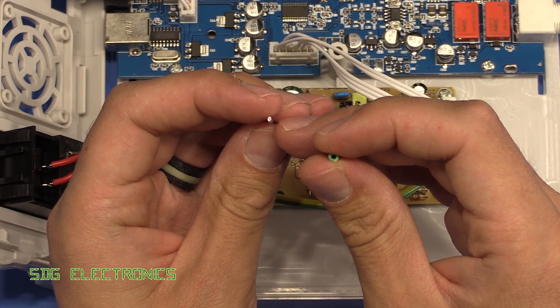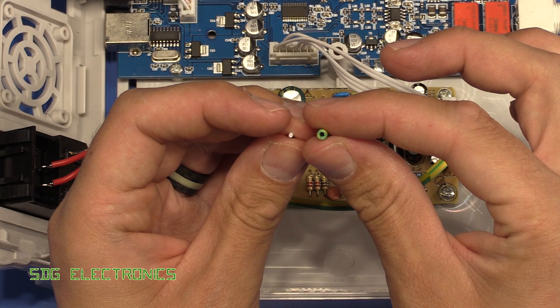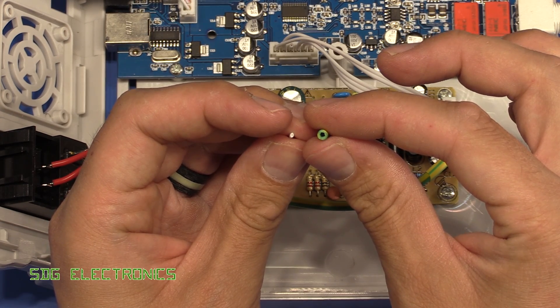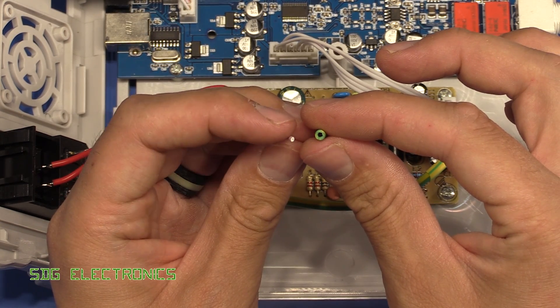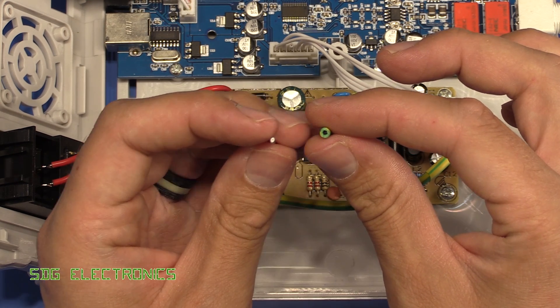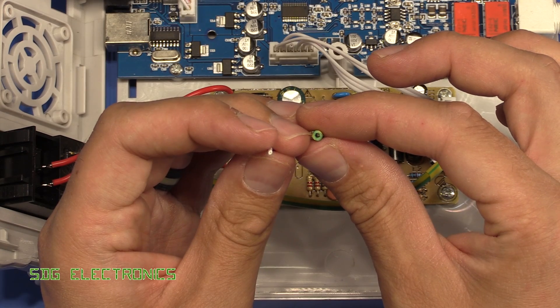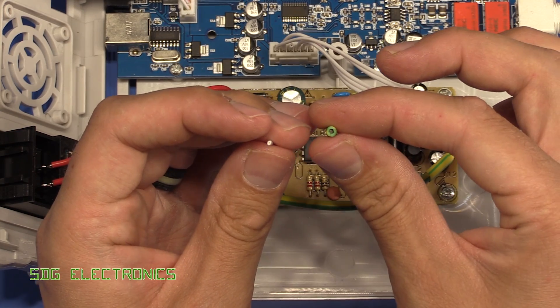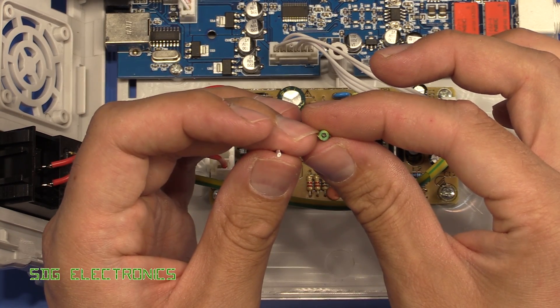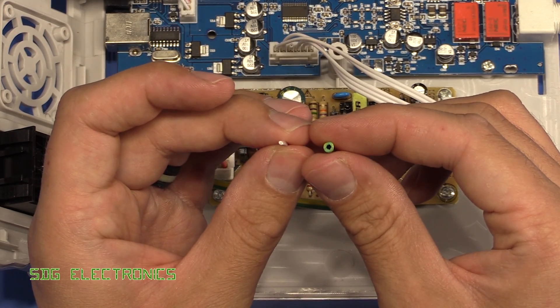Just to illustrate the point, here's the ribbon cable wire that was being used previously and this is the earth wire. You can see the difference in insulation thickness is quite considerable. The insulation thickness is independent of the current carrying capability of the wire. So even though this is quite thick, I think it's 1.5mm square, if you used 0.5mm square wire it should still have this same insulation thickness, which this one does not.